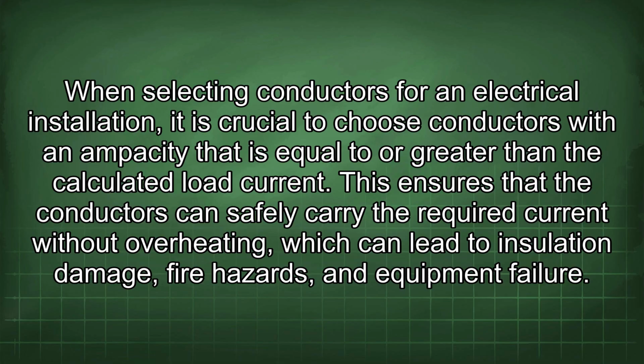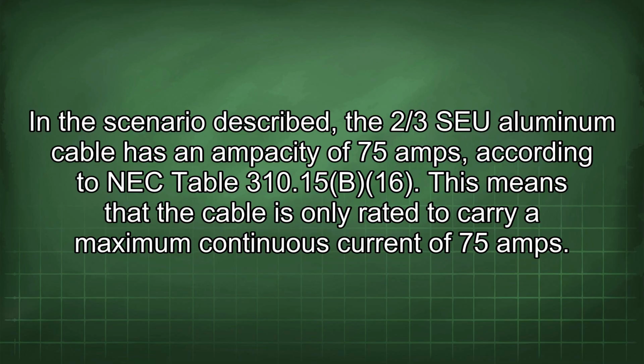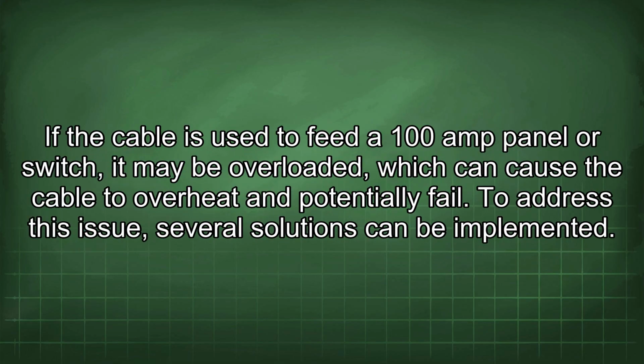When selecting conductors for an electrical installation, it is crucial to choose conductors with an ampacity that is equal to or greater than the calculated load current. This ensures that the conductors can safely carry the required current without overheating, which can lead to insulation damage, fire hazards, and equipment failure. In the scenario described, the 2/3 SEU aluminum cable has an ampacity of 75 amps according to NEC Table 310.15(B)(16). This means that the cable is only rated to carry a maximum continuous current of 75 amps. If the cable is used to feed a 100 amp panel or switch, it may be overloaded, which can cause the cable to overheat and potentially fail.